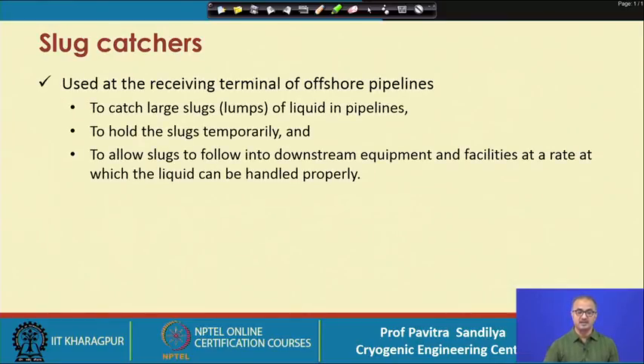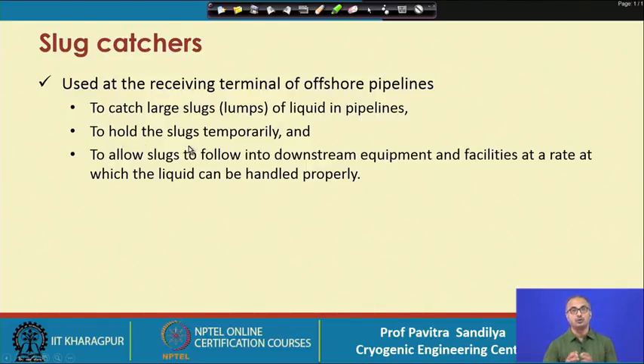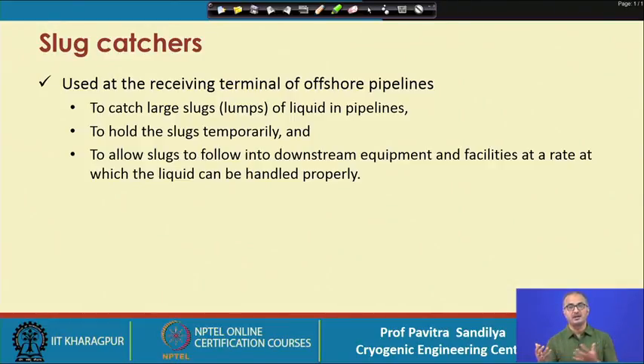Slug catchers are generally used at the receiving terminal of offshore pipelines — when gas arrives onshore from offshore, slug catchers handle water slugs, which are large lumps of liquid in the pipelines. The slug catchers catch and temporarily hold these slugs after separation, then release them to downstream equipment and facilities at a controlled rate that the liquid handling system can manage. This controlled release is necessary because if all slugs were allowed to pass downstream at once, the downstream equipment may not be able to handle them.